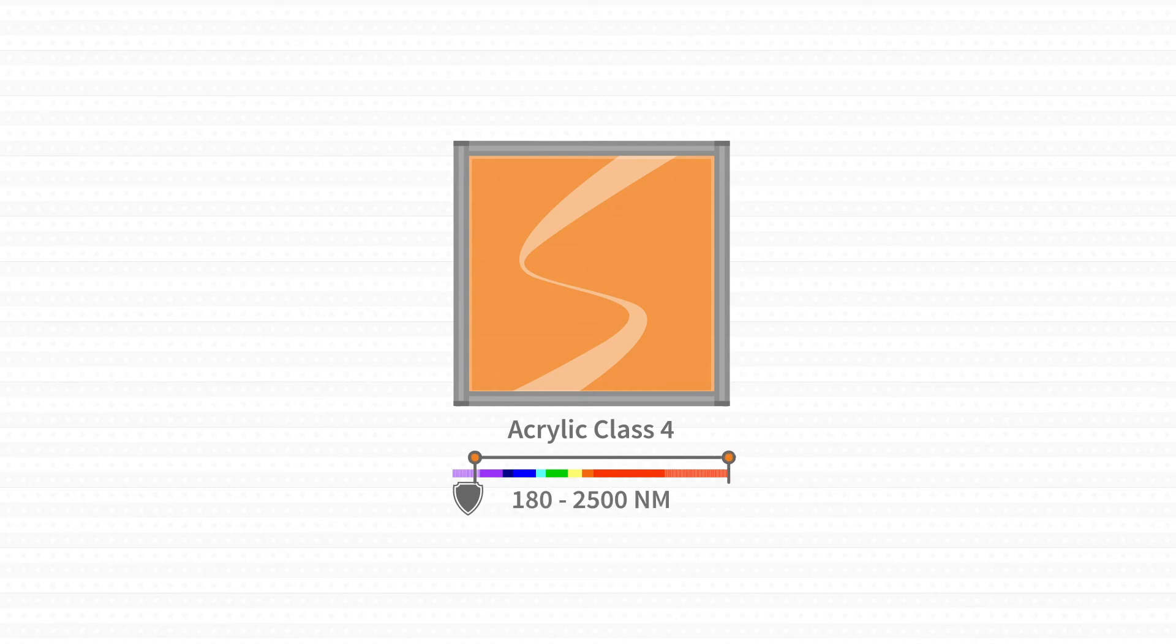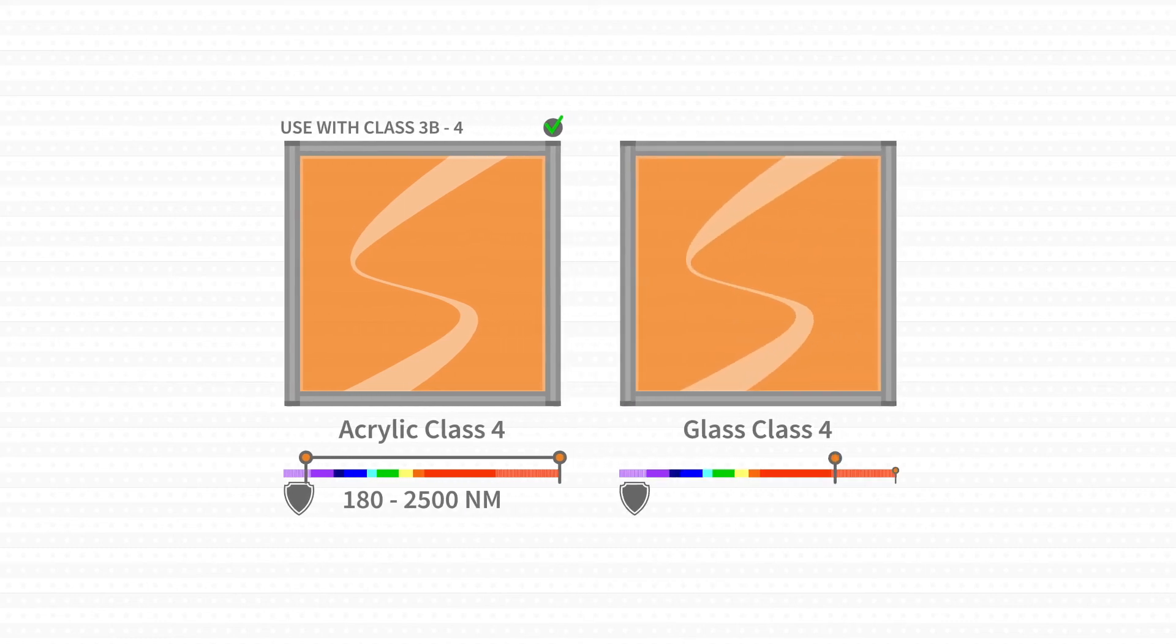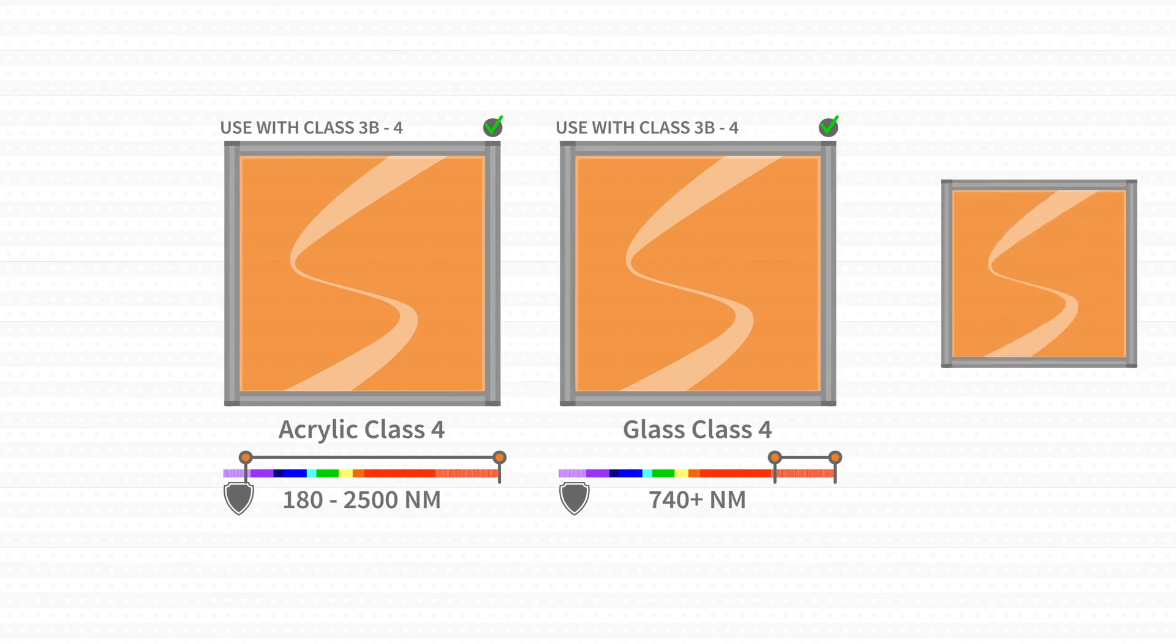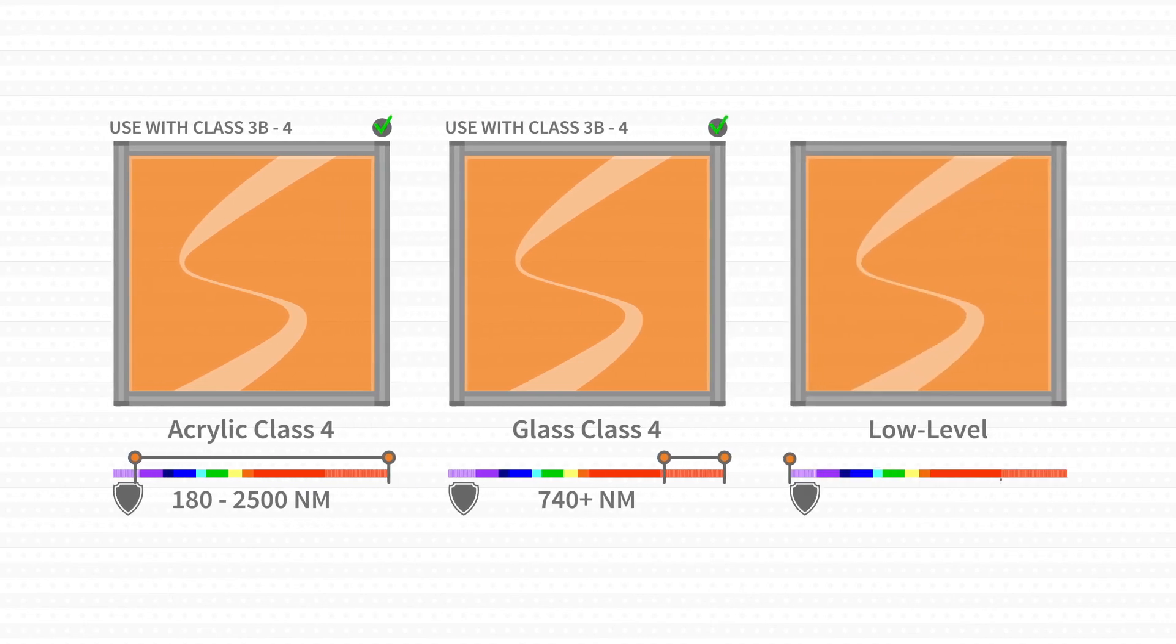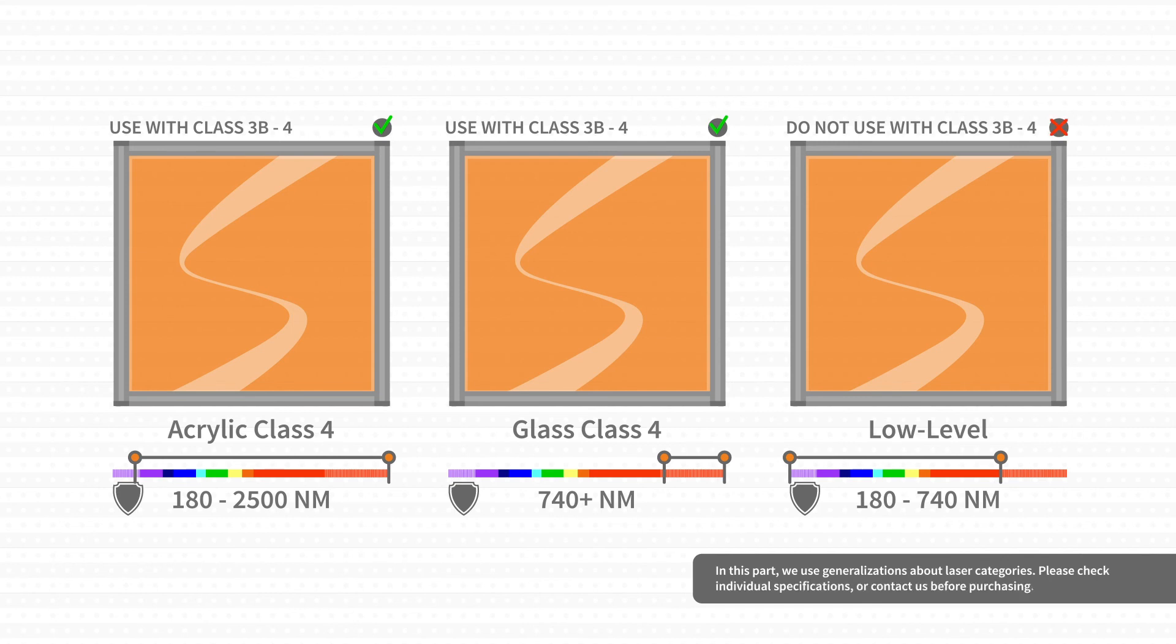Acrylic class 4 windows generally protect from ultraviolet, visible light, and near-infrared lasers. Our glass windows protect from primarily infrared lasers. Low-level laser windows protect from low-level ultraviolet and low-level visible light.